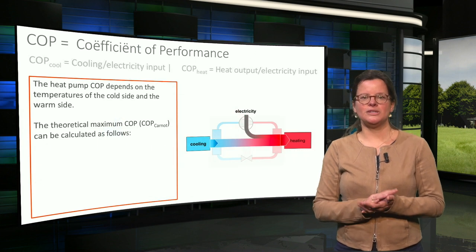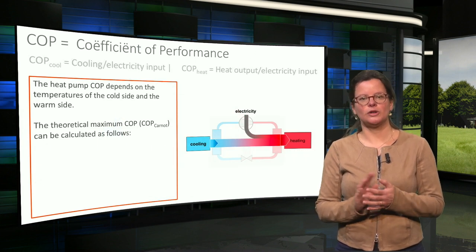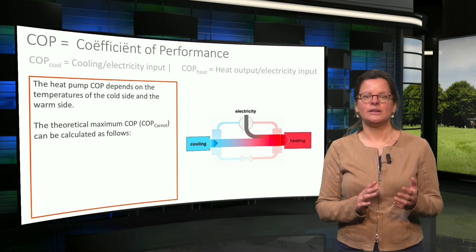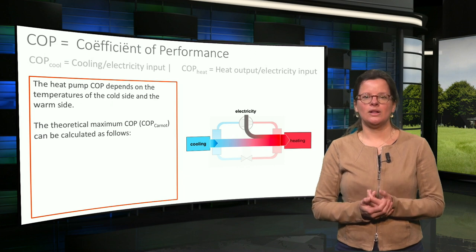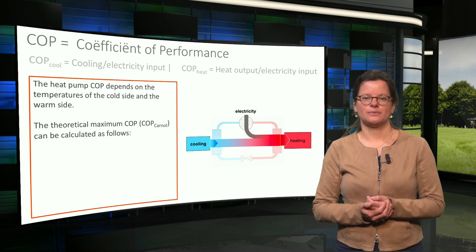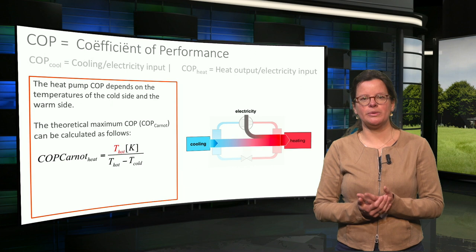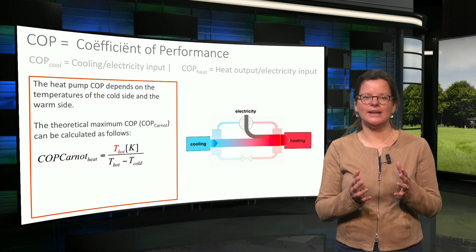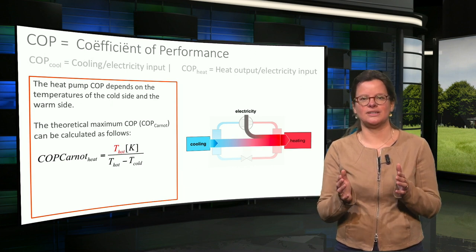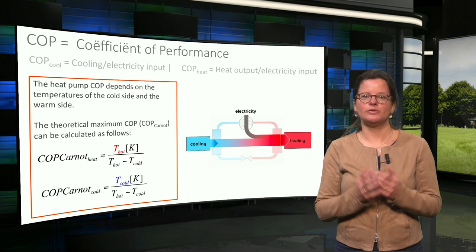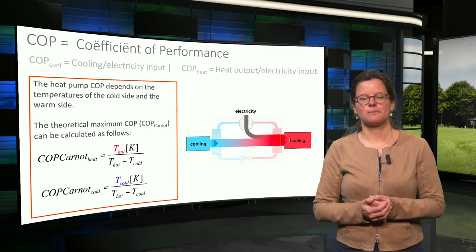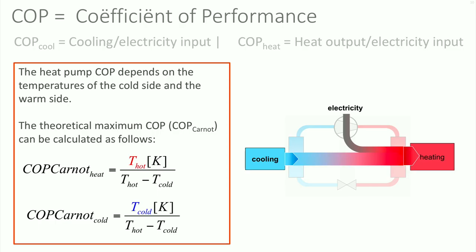The achievable heat pump COP depends on the temperatures of the cold side and the warm side. The theoretical maximum COP, which is called the COP Carnot, can be calculated based on the temperatures. The maximum COP for heating is determined by dividing the high temperature by the delta T, and the maximum COP for cooling is determined by dividing the temperature of the cold side by the delta T. Please note that the Kelvin scale must be used for the temperatures.